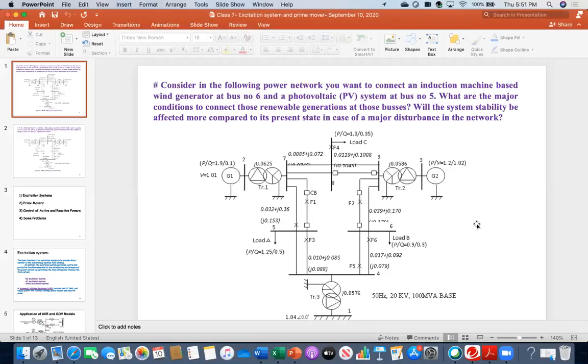So now go back there again. What about the frequency stability - is there any effect? The frequency might go high again, might not come back to the original position. Sometimes, for example in the United States, frequency is 60 hertz. After some oscillation, frequency came back, but settled at 58 hertz or 62 hertz. It's still stable, but might not come back to the original position because voltage has gone significantly low. That is the impact.